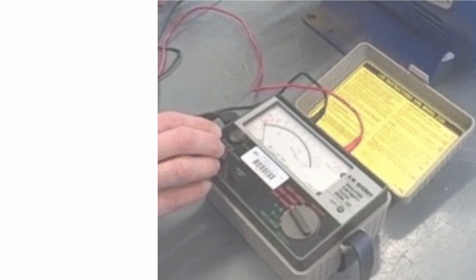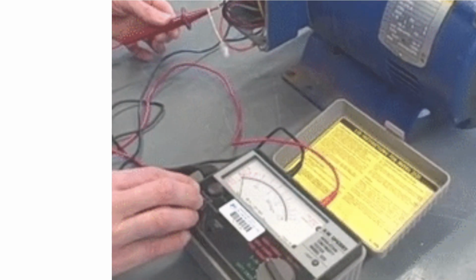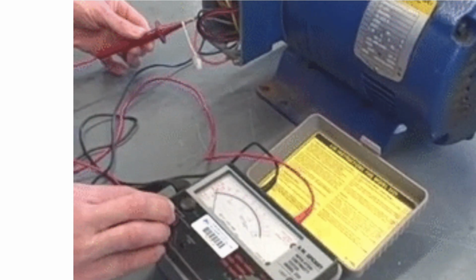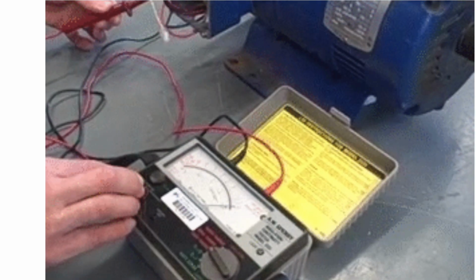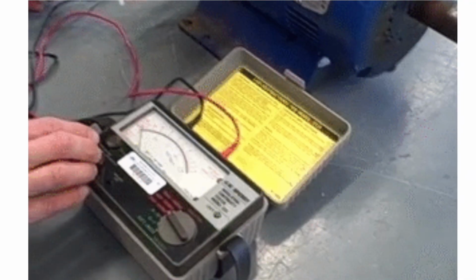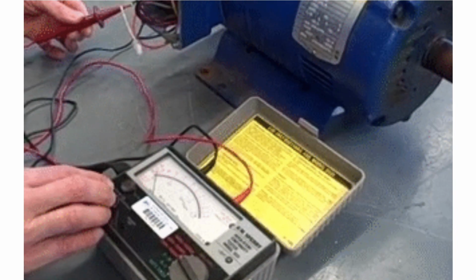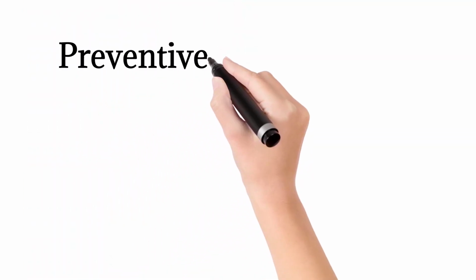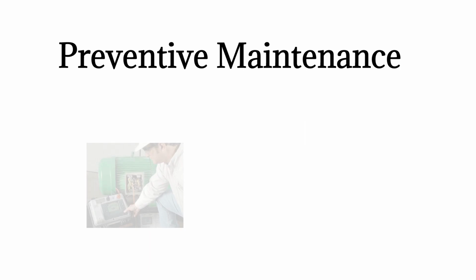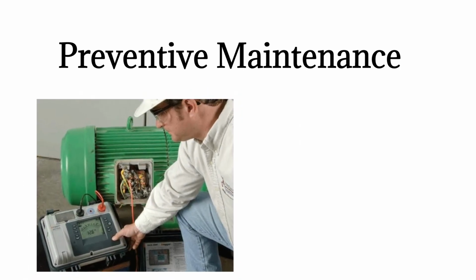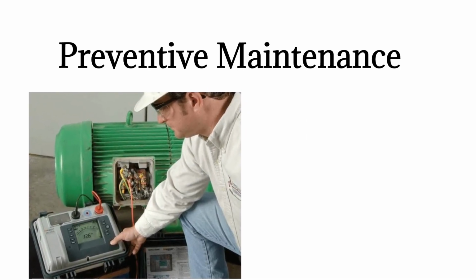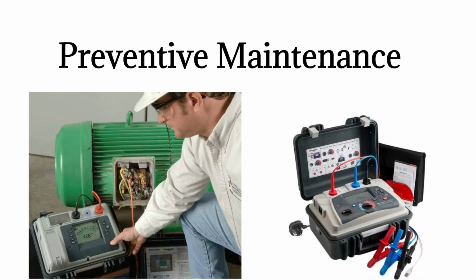A very high resistance reading greater than 10 megohms will indicate the motor insulation is good. It is recommended to consult with the motor manufacturer's user manual if required. Repeat the steps with the other two phases. The periodic measurement of the resistance of the insulation will indicate the state of the motors and when it is necessary to replace or modernize them.